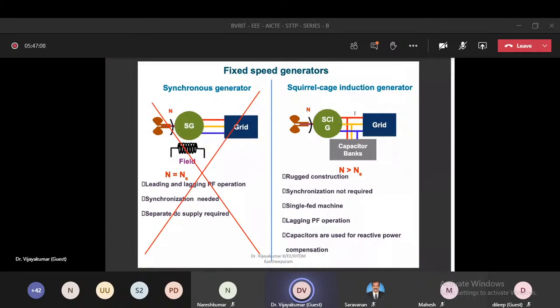Next one is squirrel cage induction generators, the normal squirrel cage machines. When you connect these squirrel cage machines to the grid, it will act as a motor. It will rotate at no-load speed. For a 4-pole machine on a 50 hertz supply system, it may rotate at 1480 RPM. Am I right? 1480 RPM, in the clockwise direction. You can consider the clockwise direction.